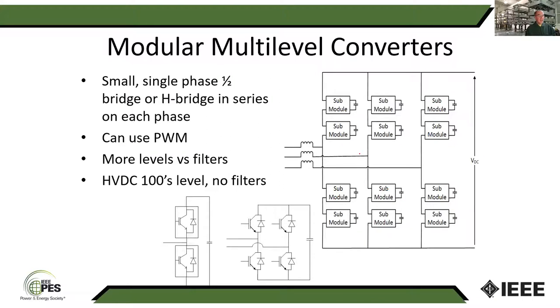So in some ways, especially with things like HVDC converters, they used to be kind of equivalent to steam locomotives, where each railroad would order a custom design of a locomotive with certain features that they wanted that were unique, and the manufacturers would build it to those specs. When General Motors started producing the first diesel electric locomotives, they basically said, this is our standard module. We're not going to do custom modules. And that allowed them to mass produce common designs. And if they made modifications, they would have slightly different versions of them, but they didn't do customized ones. Like when they came out with new releases, it might be changing some of the controls or putting in bigger motors or things like that. Modular multi-level converters are the same way.